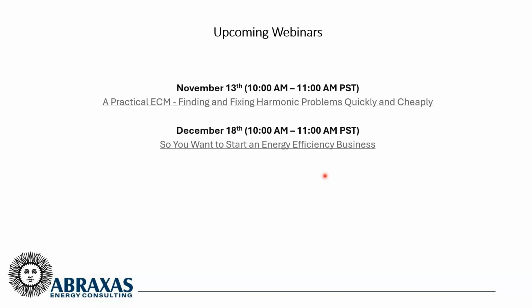Okay, here's the first one. Is motor load essentially load factor? I see 70% used as an assumption. Yeah, the 70% I used in the equation was just a number. Typically motors, when they're designed for a load, are loaded 70 to 80% to meet the maximum efficiency for that motor. If you go much higher, you're running into heat issues because of the insulation class. You want to be careful not to exceed the insulation class on the temperature. And as you get lower, of course, you have the power factor issue. So it's good to operate somewhere in that 70 to 80% as a design guideline.